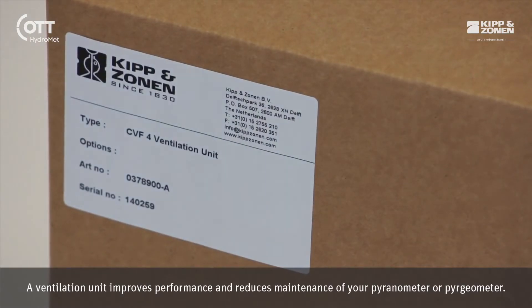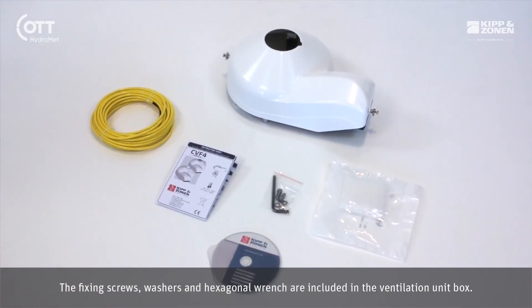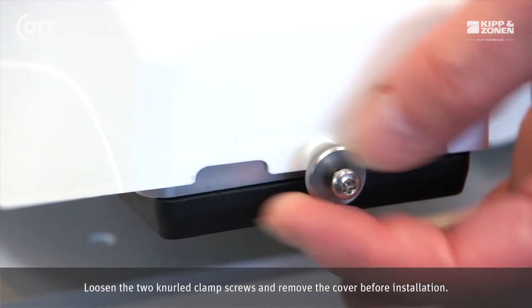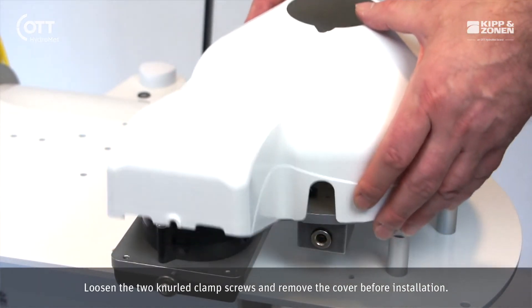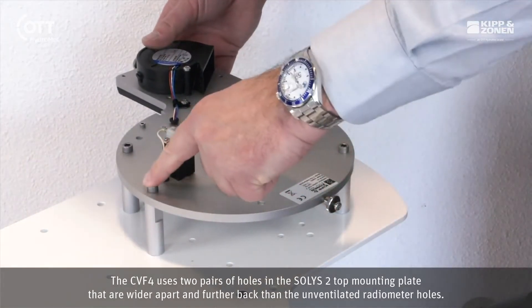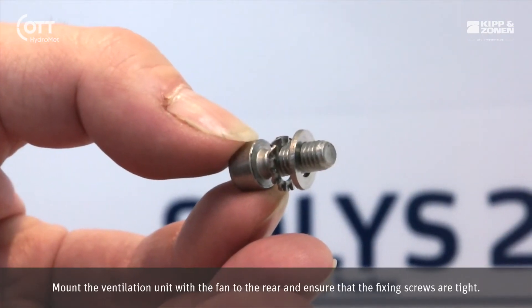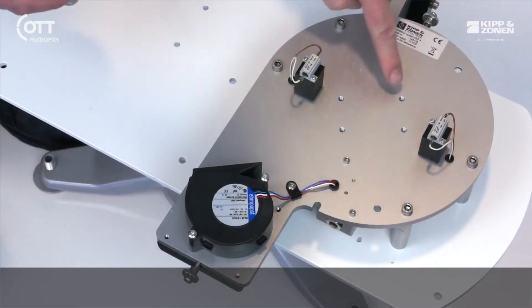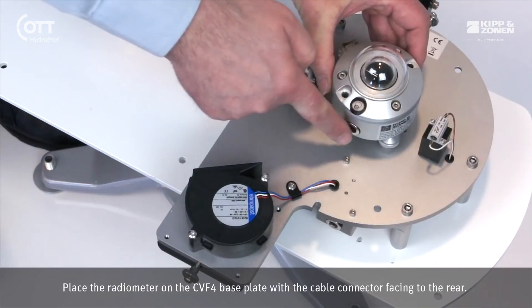The ventilation unit improves performance and reduces maintenance of your pyranometer or pyrgeometer. The fixing screws, washers and hexagonal wrench are included in the ventilation unit box. Loosen the two knurled clamp screws and remove the cover before installation. The CVF4 uses two pairs of holes in the SOLYS 2 top mounting plate that are wider apart and further back than the unventilated radiometer holes. Mount the ventilation unit with the fan to the rear and ensure that the fixing screws are tight. Place the radiometer on the CVF4 base plate with the cable connector facing to the rear.